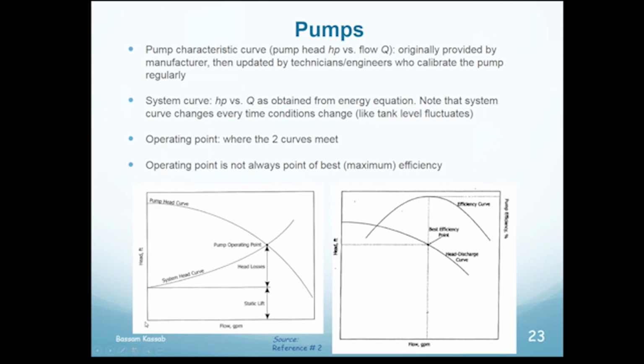So that's the curve. When the flow is very small or even zero, it's called the shut-off head, this point. Then the head goes down - the more the flow, the less the head the pump can get. And that makes sense, right? The pump curve comes with the pump when you buy it from the manufacturer. But if you have one of those big pumps that you're using for a city or a town, you want to calibrate it every year to make sure whether that curve has changed or not because of the operation of the pump, and things may change. That's why technicians or engineers calibrate the pump typically every year.